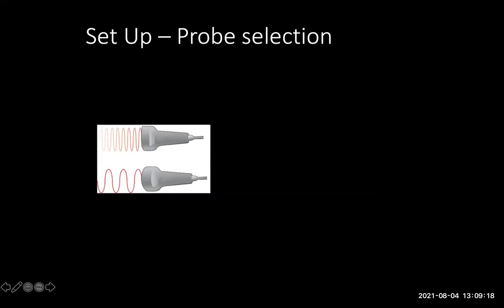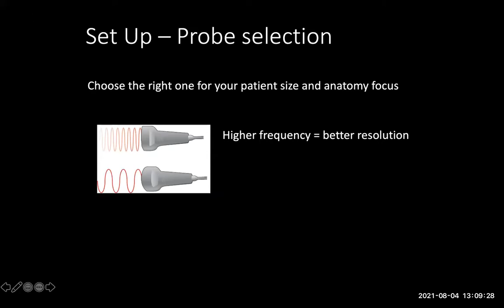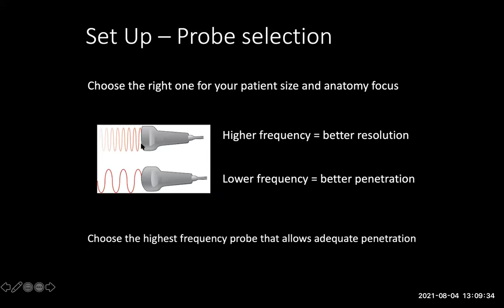There are multiple cardiac ultrasound probes available, and we want to choose the right one for your patient's size and anatomy focus. Now, the higher the frequency of the probe, the better the resolution, whereas the lower the frequency of the probe will get better penetration. So the goal is to choose the highest frequency probe that allows adequate penetration.